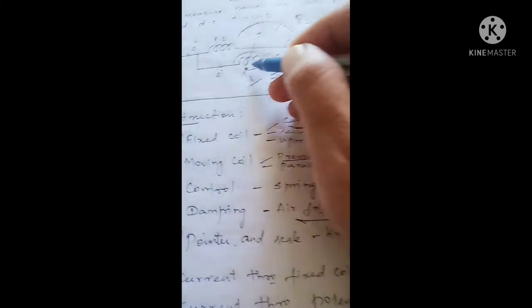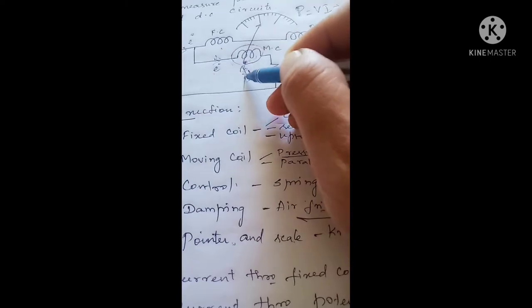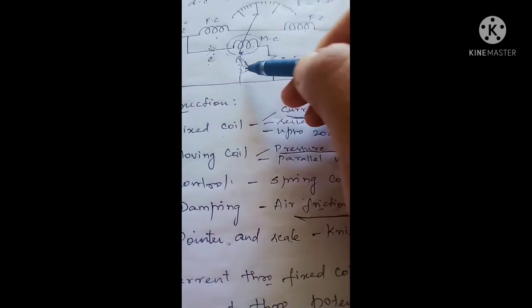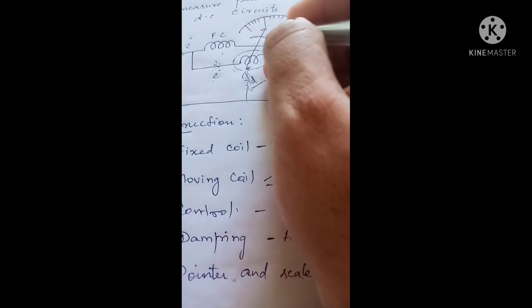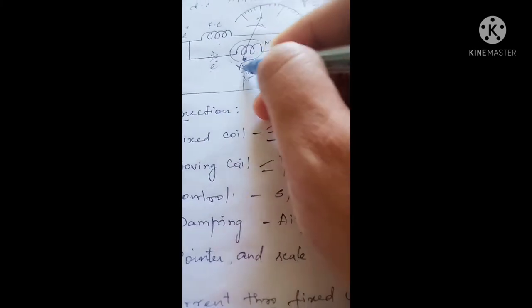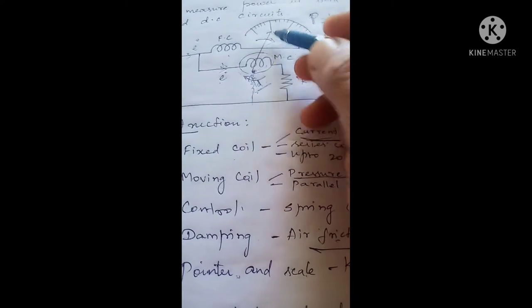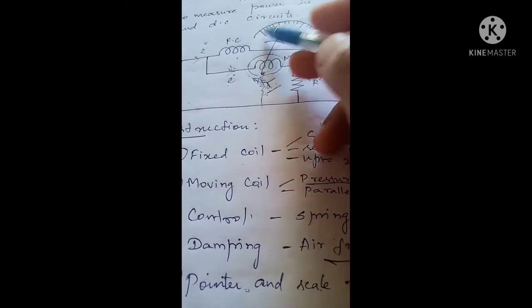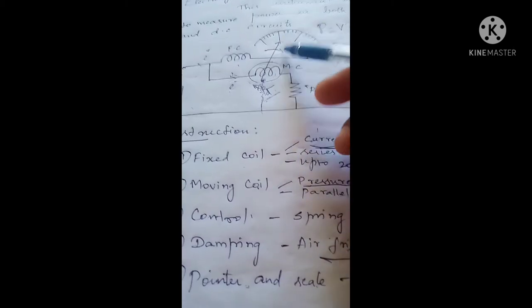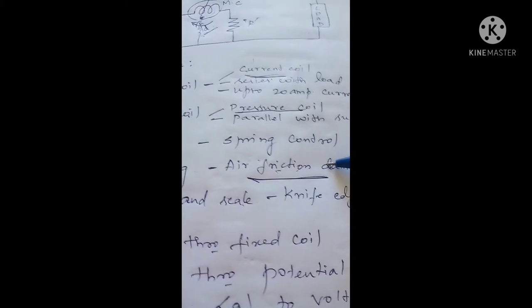The deflecting torque is opposed by the spring arrangement at the bottom of the moving system, which produces an opposing force. When the deflecting torque and spring force get balanced, the pointer comes to a steady position. Any remaining oscillation of the pointer over the scale is reduced by means of air friction damping.